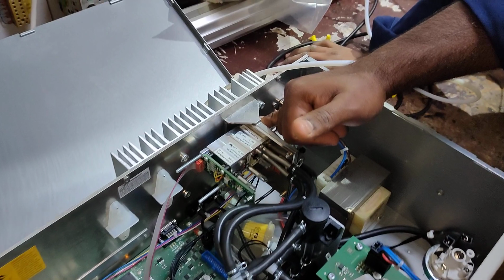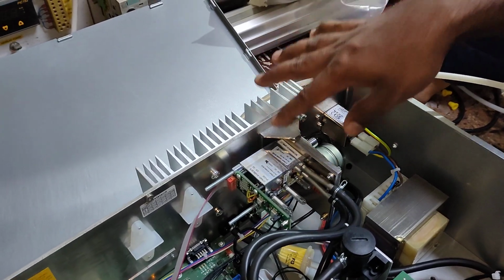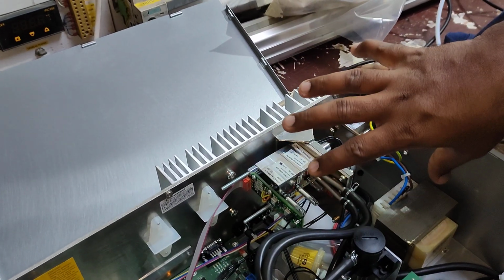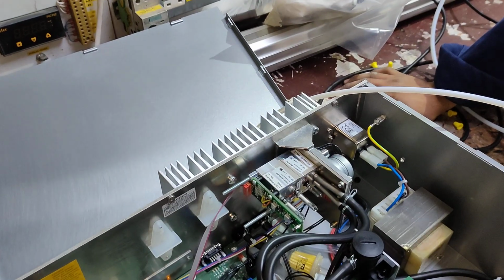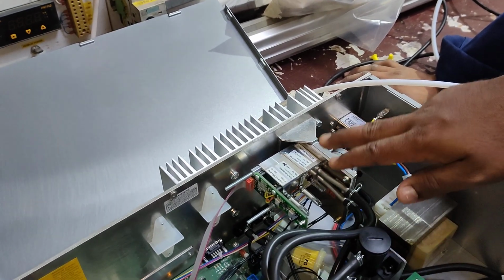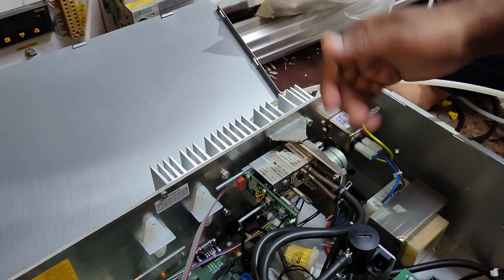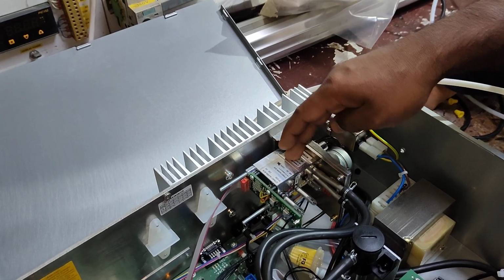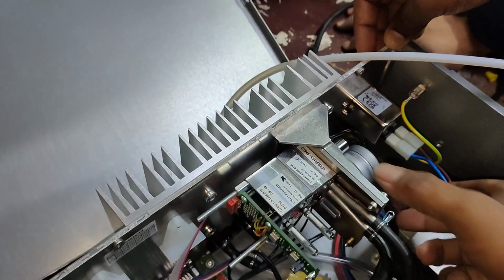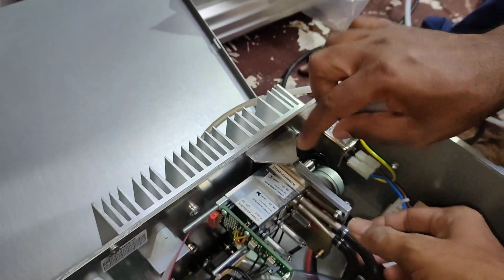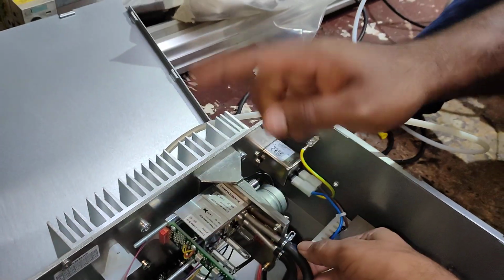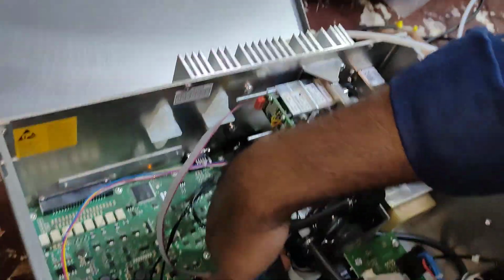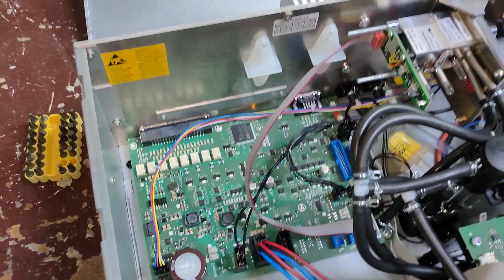Don't try to replace the IR source and detector fixed inside. You remove this whole assembly outside and then you replace it, because you don't have space. Otherwise you will try to do this and you will damage some other things. So when we remove these three screws, the whole body will come outside. But first you have to remove the hose pipes, 1, 2, 3, 4 hose pipes.